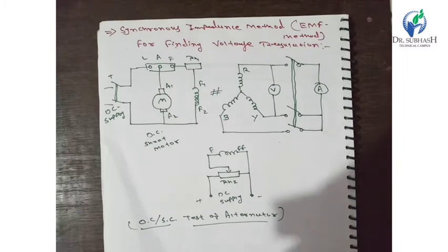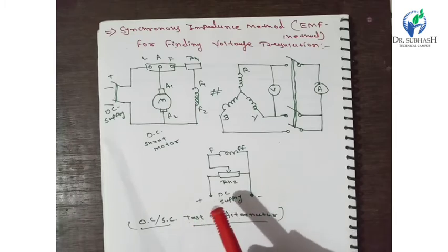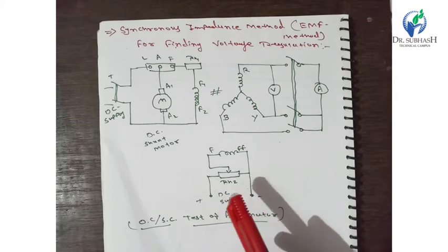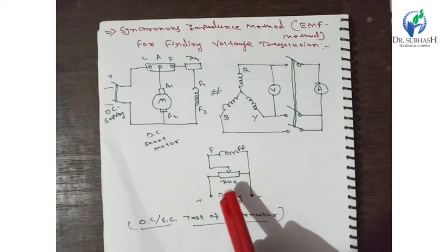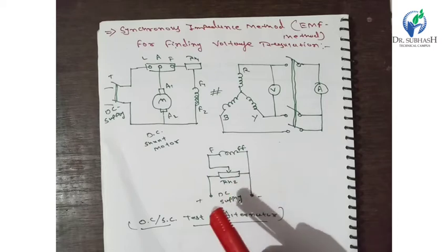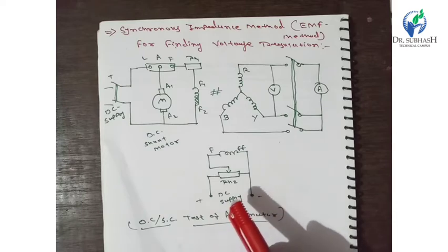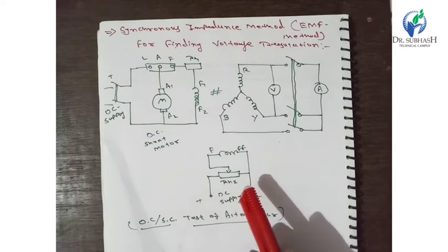This method graphically estimates the voltage drop by determining the synchronous impedance and reactance, which include the leakage reactance and the reactance proportional to the armature reaction. The method helps to estimate the voltage regulation indirectly, to a limited degree of accuracy, especially for large alternators where direct loading is not possible.